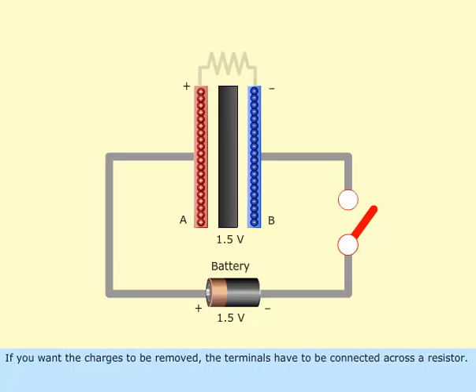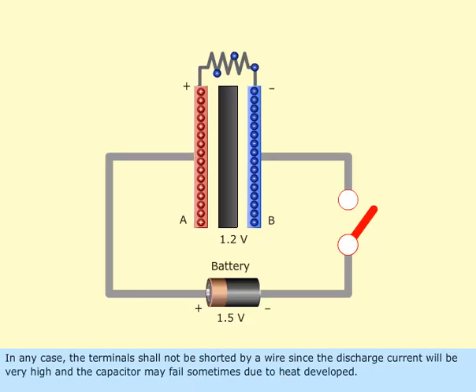If you want the charges to be removed, the terminals have to be connected across a resistor. In any case, the terminals shall not be shorted by a wire since the discharge current will be very high and the capacitor may fail sometimes due to heat developed.